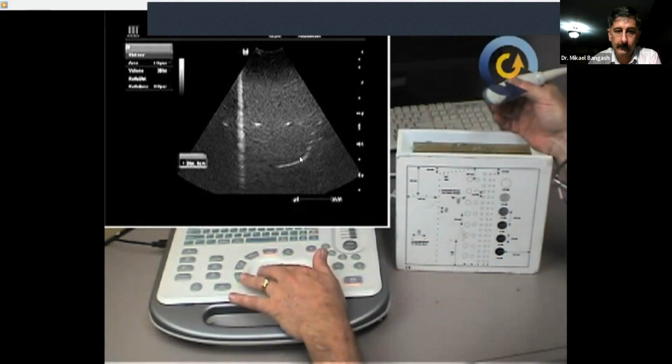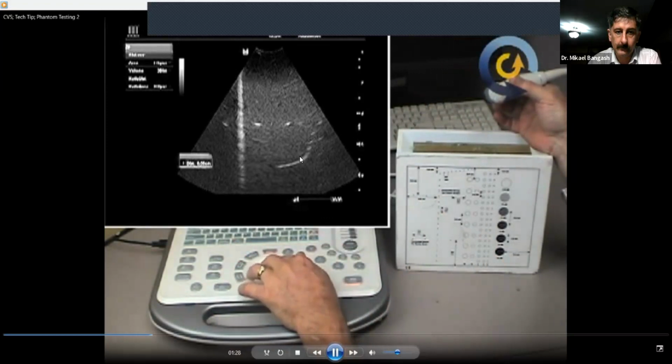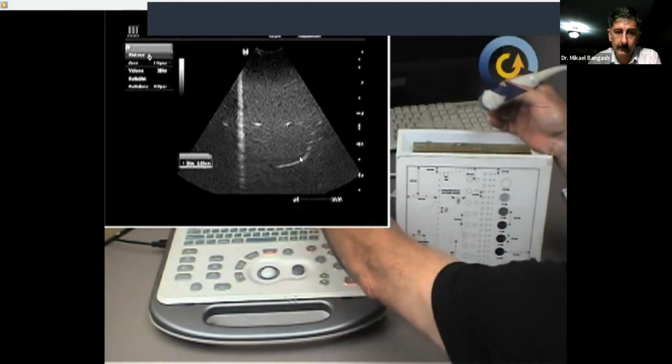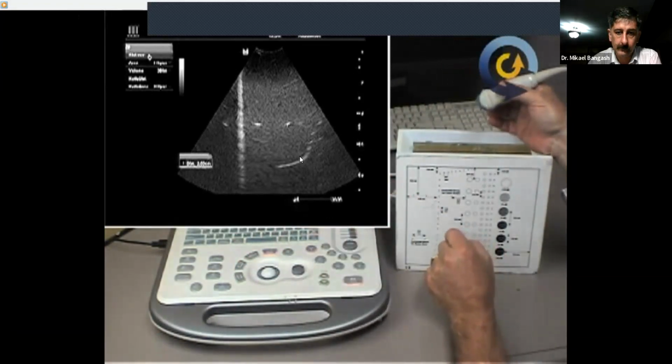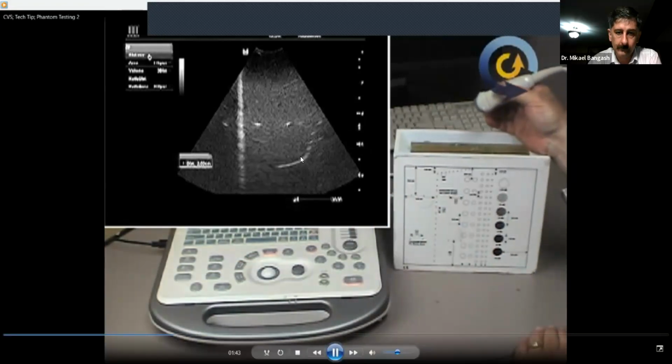What you'll end up doing is making an educated guess that it's center to center. It's measuring 2.03, and that's a 2 centimeter distance up here, so again, that's very accurate. You could do the math on the percentage, but it's a very good measurement, and it shows it's not off. That's critical, and you want to document that.